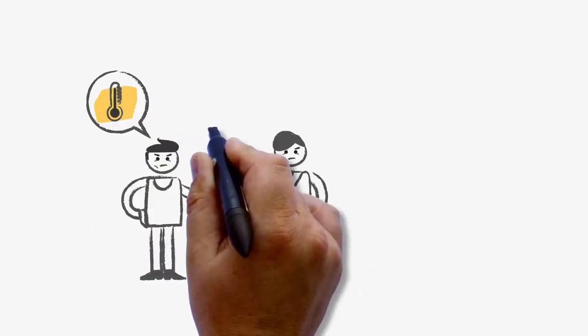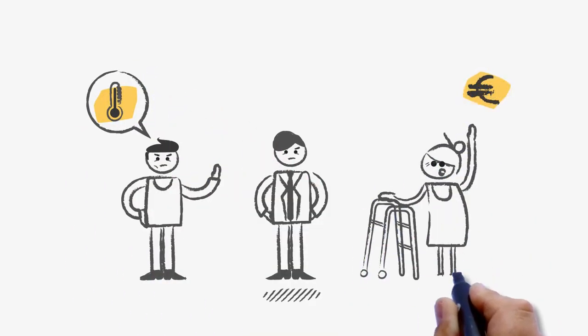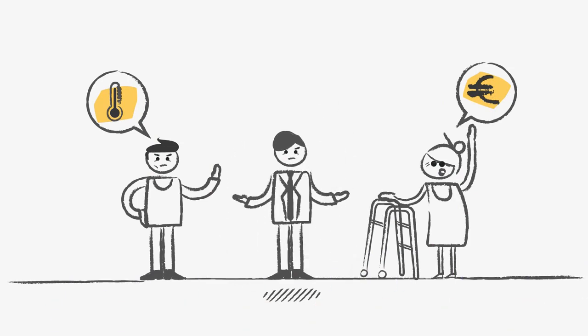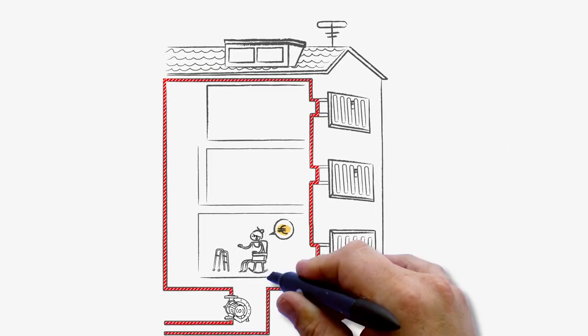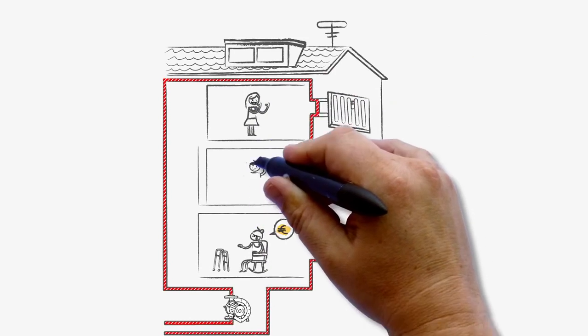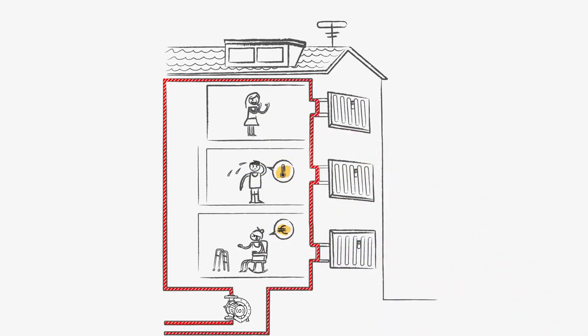you're probably familiar with complaints from residents about under- and overheated rooms and complaints about high energy bills. Energy inefficiency is mainly caused by a constant flow of hot water in the heating system, regardless of whether the radiators are open or closed.